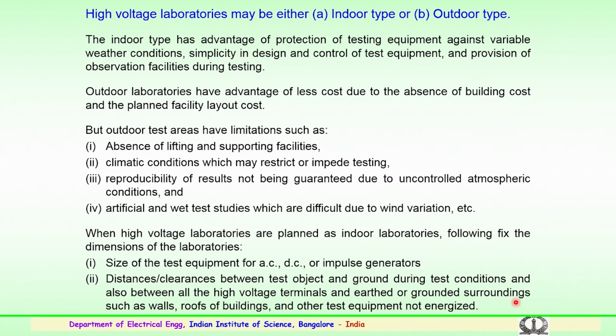The next point is that artificial and wet tests are difficult due to wind variation. Carrying out artificial pollution tests, rain tests, or wet tests on the equipment in the outdoor case will be a difficult task because of the wind direction and so on. So, it is recommended to carry out these types of tests in a closed enclosure, in a closed volume, in an indoor environment, where there are better options for reproducibility and it is also easier to carry out this experimentation.